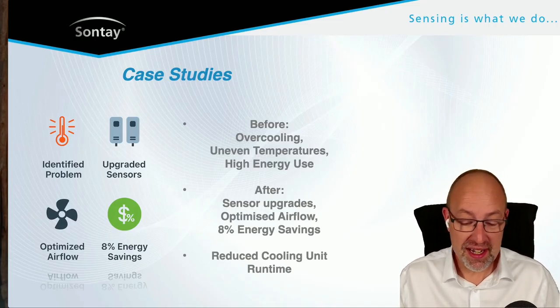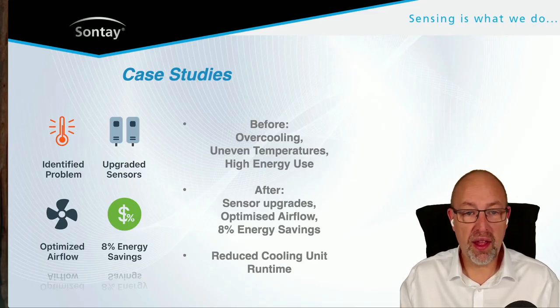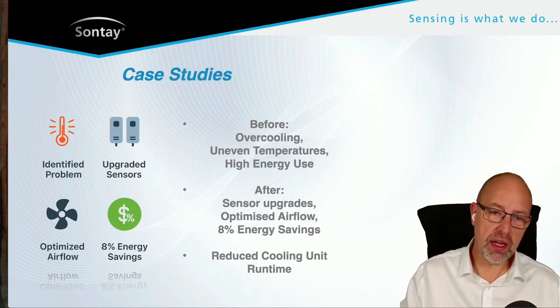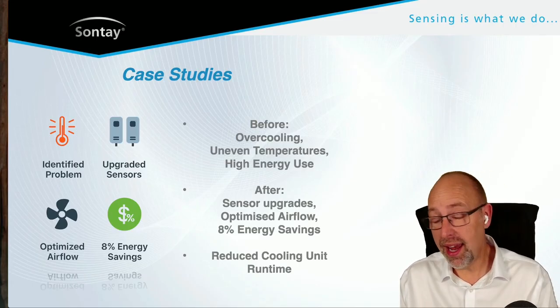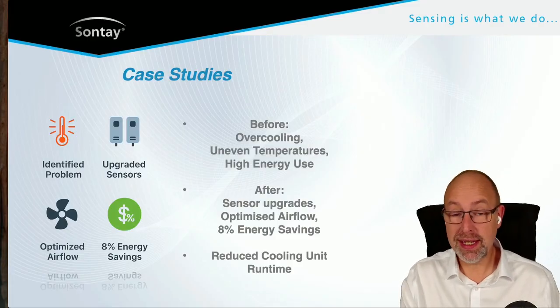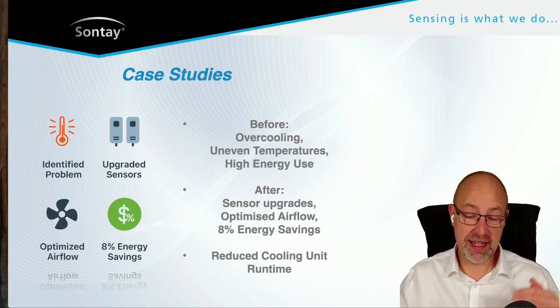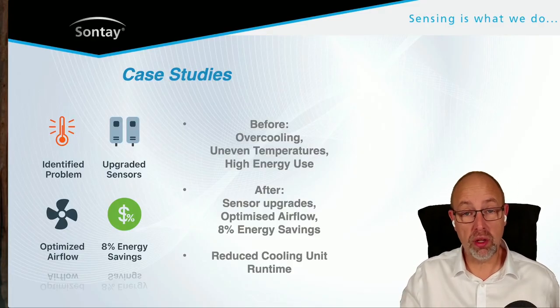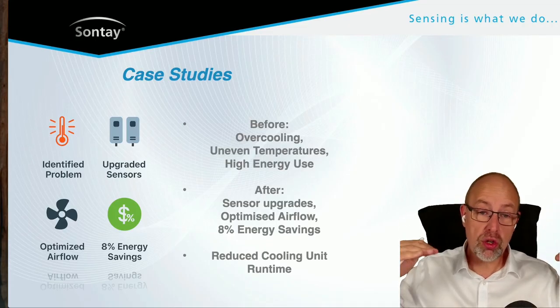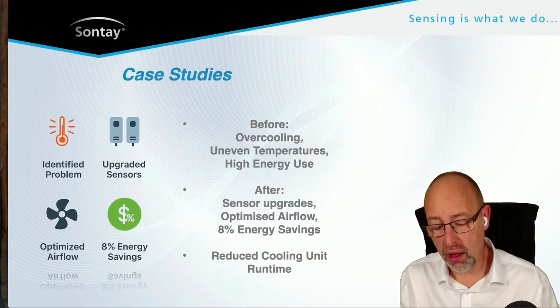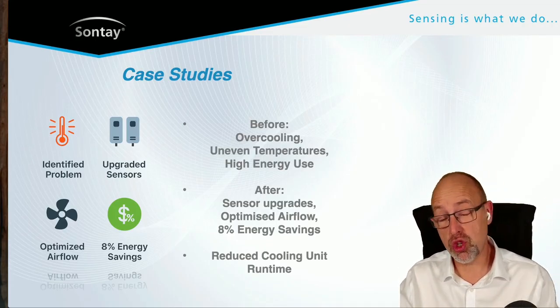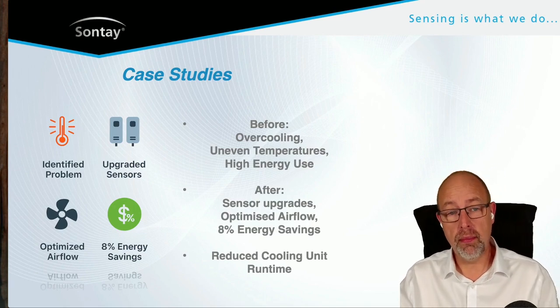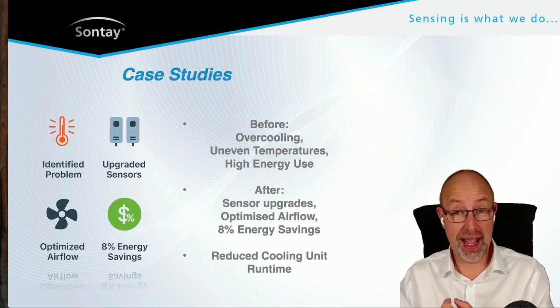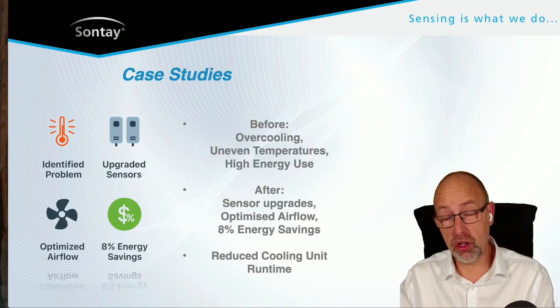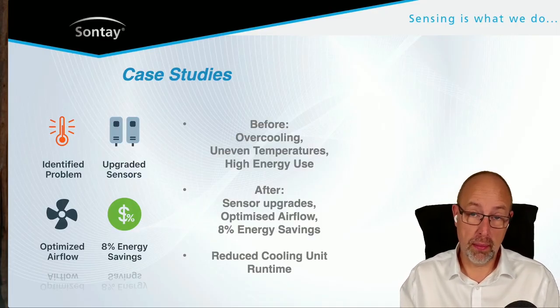There is a data center I've been told about where they were overcooling, with uneven temperatures, leading to high energy use. What they did was a wholesale upgrade of sensors—putting sensors in the cold aisles and warm aisles to look at the stratification. After the sensor upgrades, once they were sure the information was accurate, they optimized the airflow, reduced the cooling unit runtime, and saw an 8% energy saving.